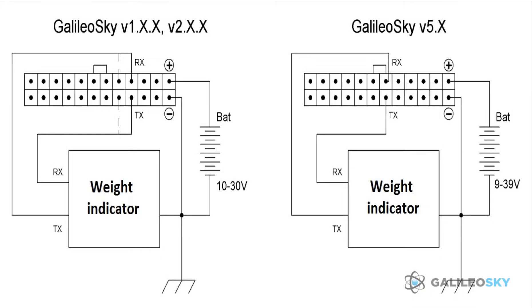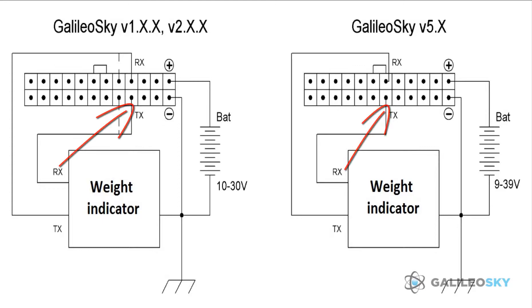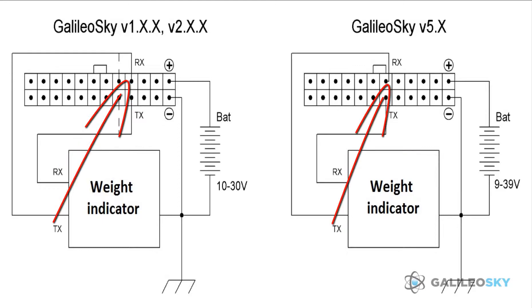Connection of the weight indicator is carried out according to the scheme. Note that the GND grounds of the terminal and indicator should be connected. RS232 contacts should be connected strictly according to the scheme: indicator RX to terminal TX, and indicator TX to terminal RX.